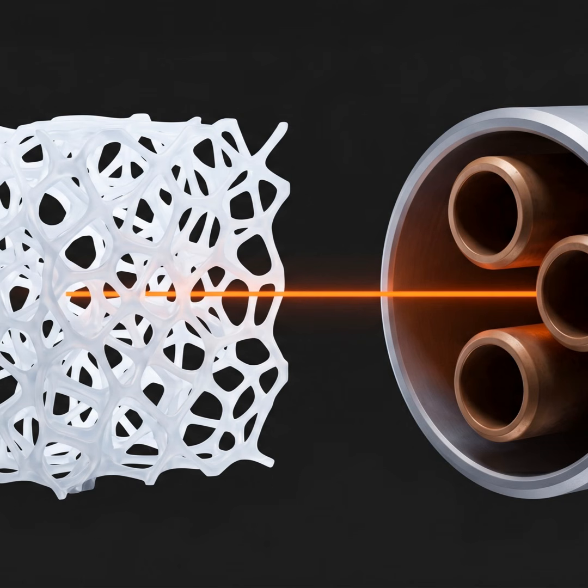So they stop paying the gas company to create heat. What is the impact on the cooling side? Because you mentioned it works on both ends. Right. The second win happens back at the refrigeration loop. Because you have intercepted that 250-degree gas and sucked the majority of the heat out of it to warm the water, the gas is already cooled down significantly before it ever reaches the condenser on the roof. Ah, so the condenser doesn't have to work as hard to finish the job.